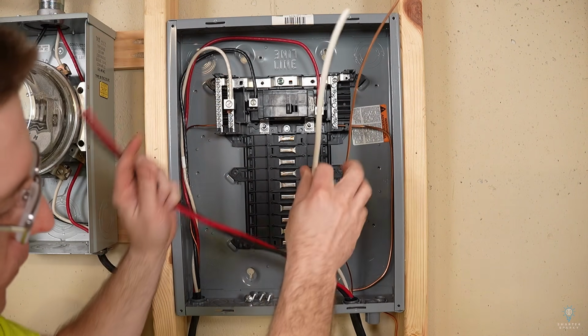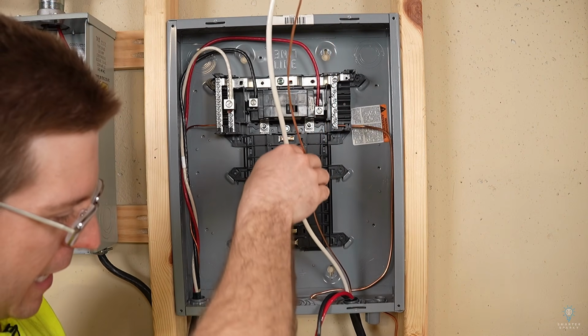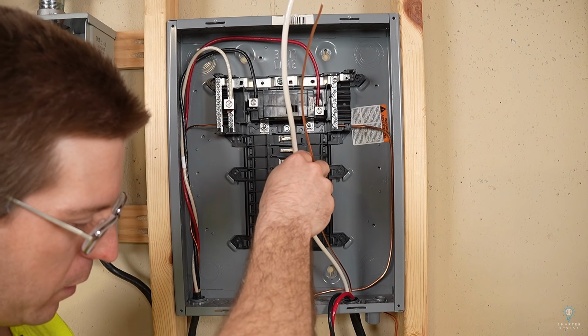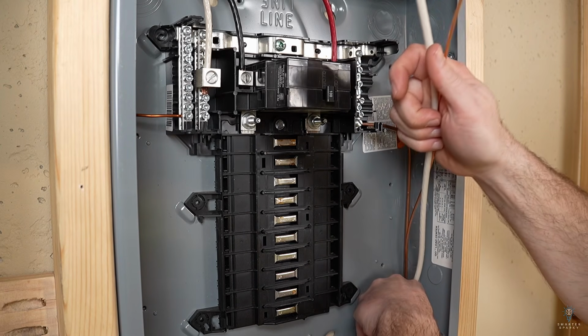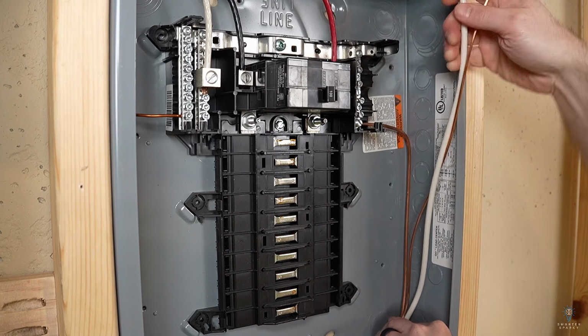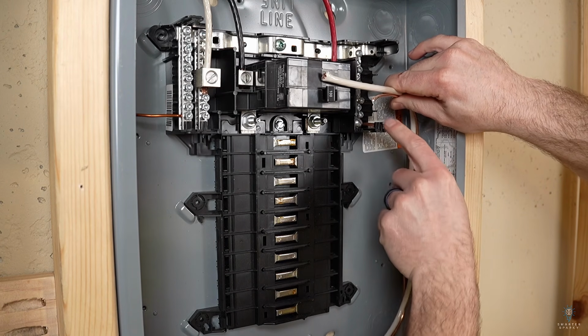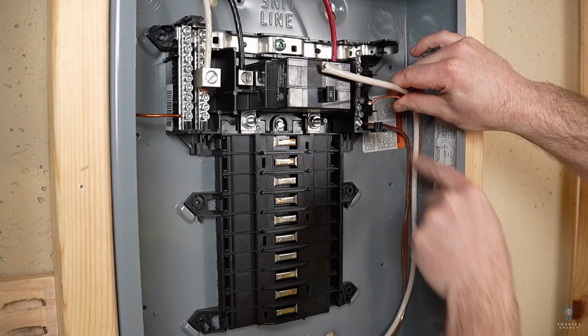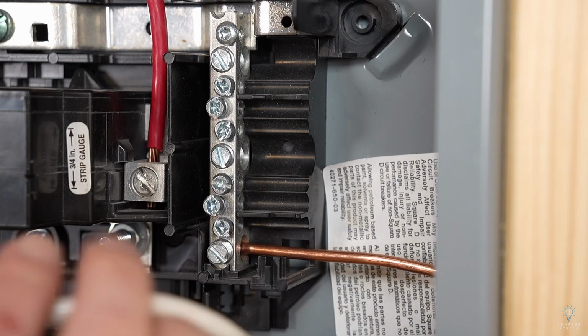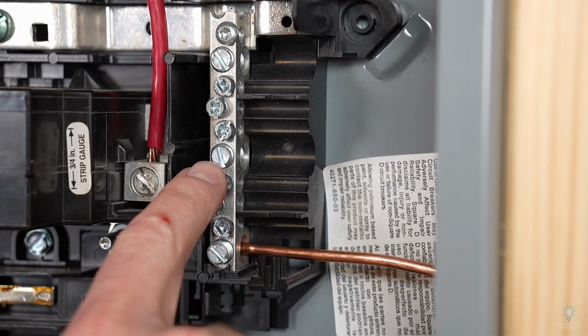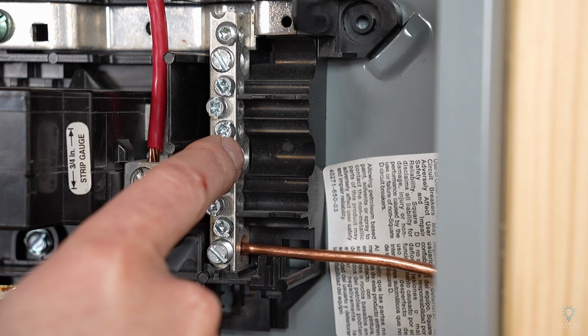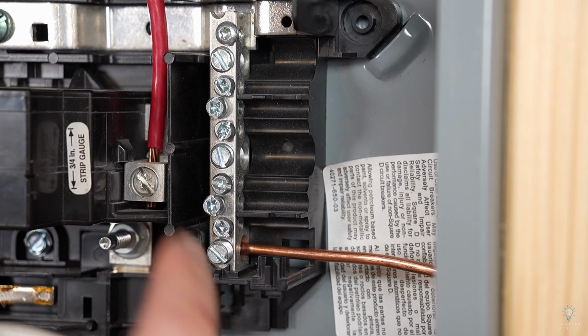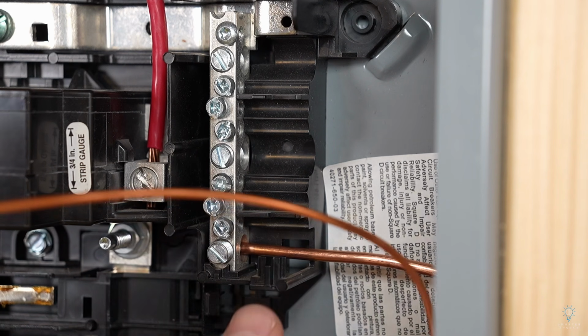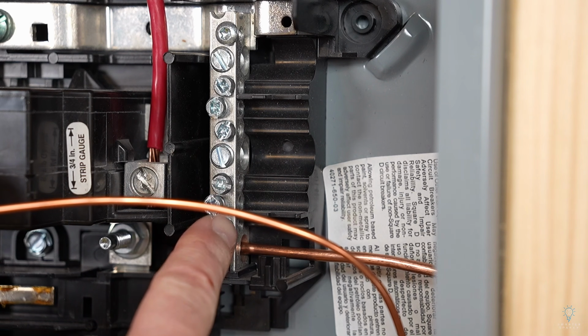So I'm going to separate out the ground and the neutral. We'll put our hots down here on the bottom, just out of our way for now. And I'm just going to manipulate that neutral and ground into the corner here and get it to bend up roughly in line with the neutral bar here. This 6-gauge wire is actually going to have to land under this larger screw here. It leaves a larger opening inside the bus bar. The 10-gauge ground can land underneath one of these smaller screws.